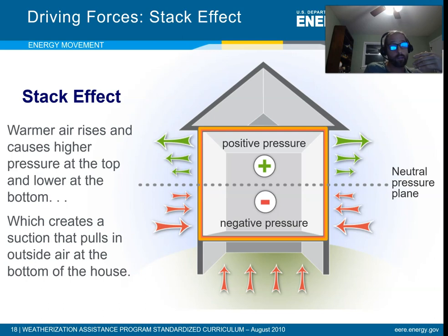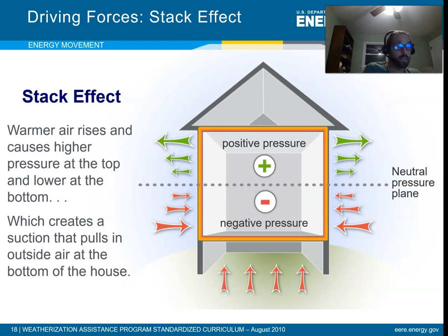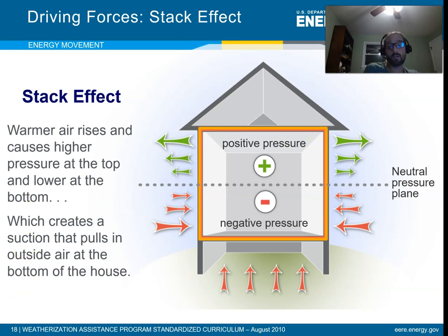For every CFM that leaves the building, another CFM has to come in, and most of that will come in toward the bottom. The only way to stop that is to prevent the air from flowing in the first place. Stack effect is really important because it happens naturally all the time in buildings, and the colder it is outside, the more likely you are to have it.